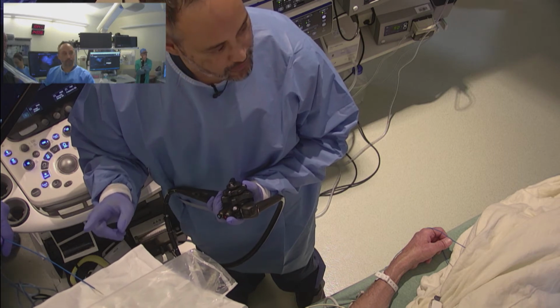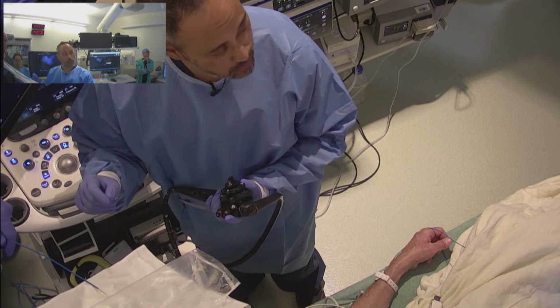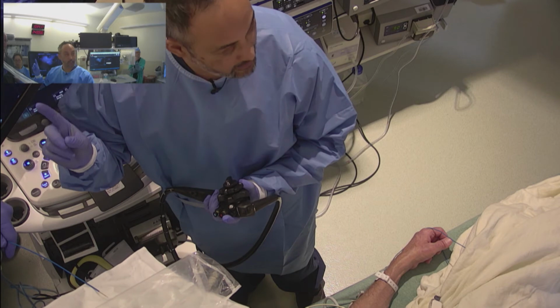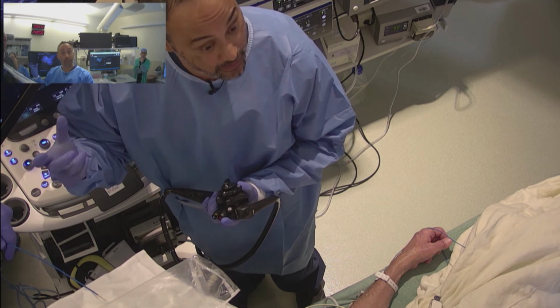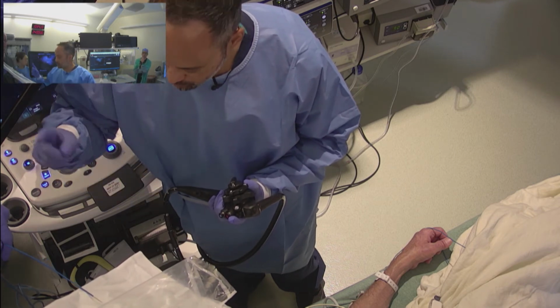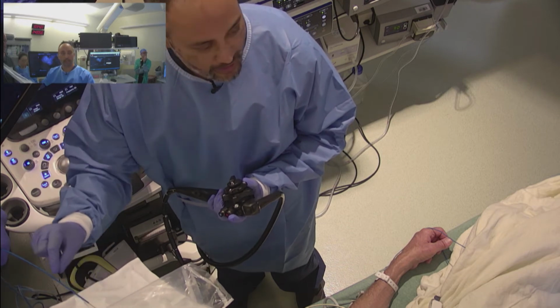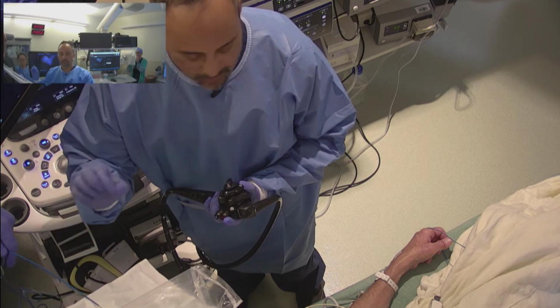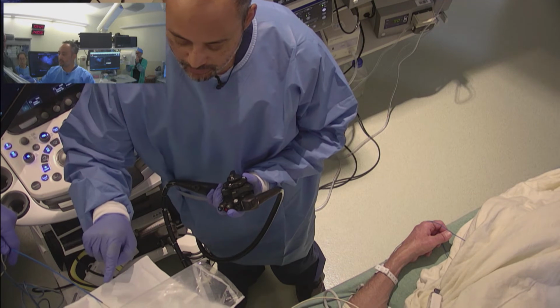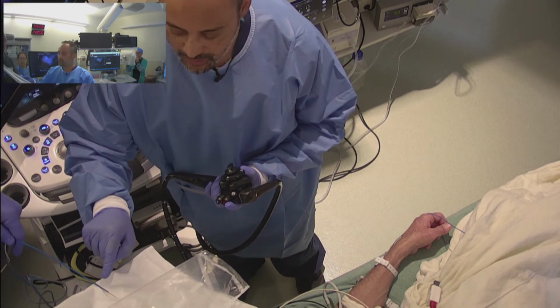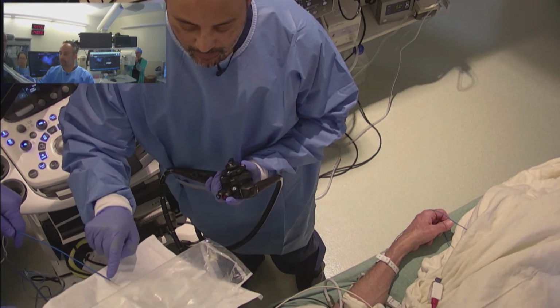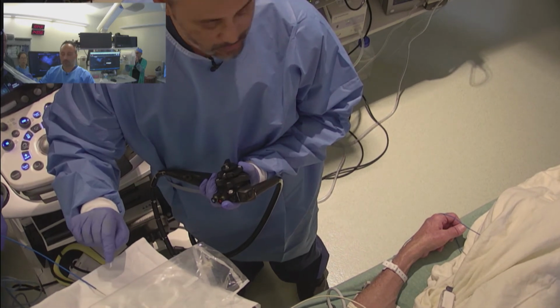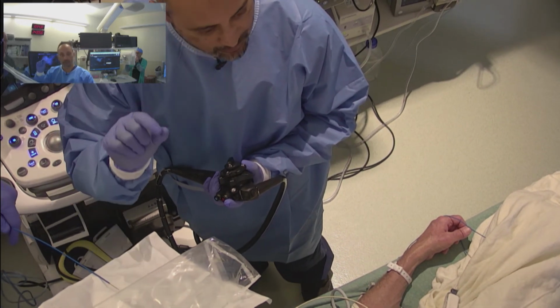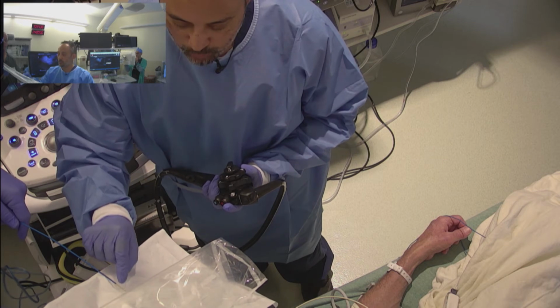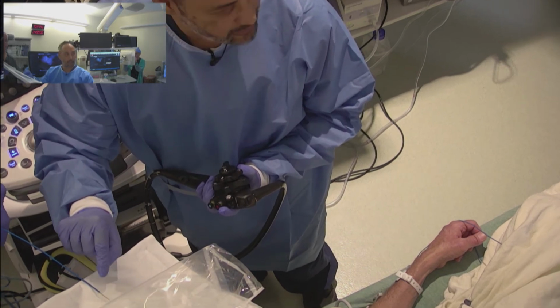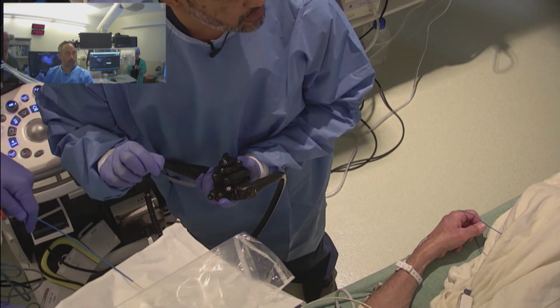This particular device is interesting because it is internally cooled, which means that we do have a bag of saline up. We tend to cool the bag of saline itself. And then it actually runs through the catheter and internally cools the catheter to mitigate the risk of charring the tissue and any collateral damage. The other thing to note, and it'd probably be difficult for you all to see, but there is an insulated tip just behind the ablation zone. So in other words, the distal tip of the catheter has 5 millimeters of ablation zone, and then the gold colored area upstream is insulated so we don't have collateral damage to the pancreatic tissue.